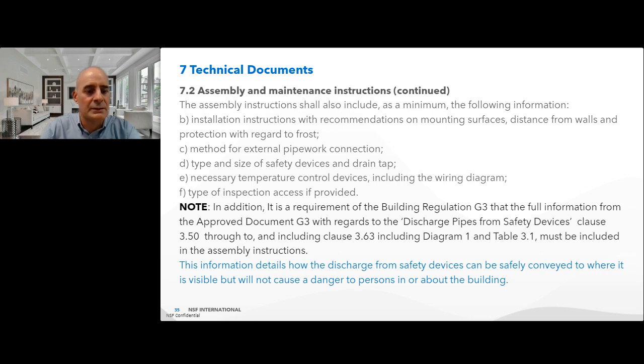Note that in addition, it is a requirement of the Building Regulation G3 that the full information from the approved document with regards to the discharge pipes from safety devices, so that's clause 3.50 through to and including clause 3.63, including diagram 1 and table 3.1 from the document, must be included in the assembly instructions. This information details how the discharge from safety devices can be safely conveyed to where it is visible, but will not cause a danger to persons in or about the building.